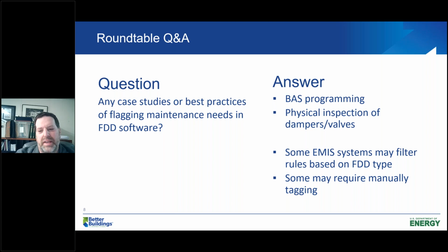But there's a caveat to this, which makes it more challenging. What's really important is to keep in mind the importance of tagging equipment with the same names throughout the process. When you have a vendor come in, they program your controls in their building automation system to operate a certain way, and they'll name an air handler a certain way. So they could call it AHU1, or they may have a name with the building attached to it also.